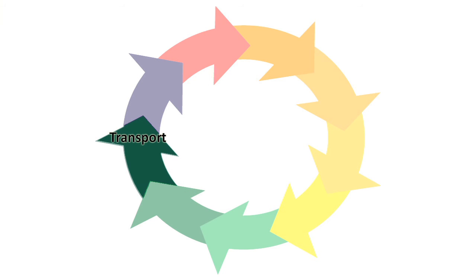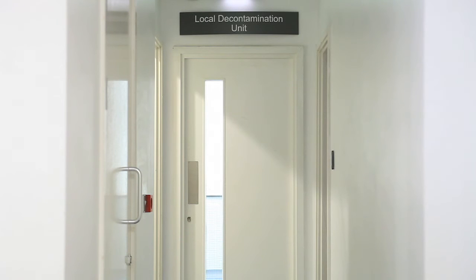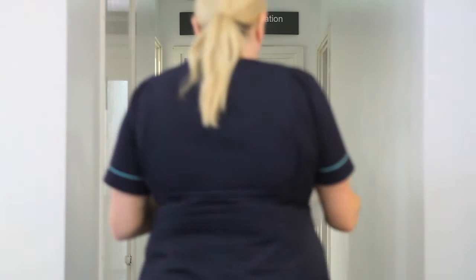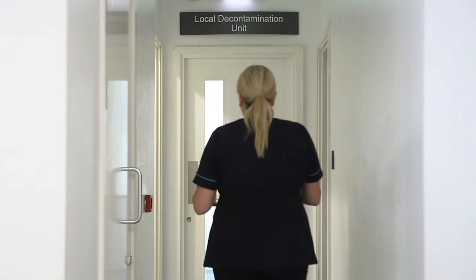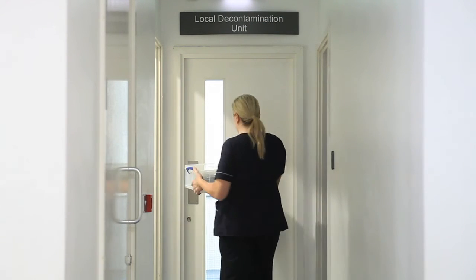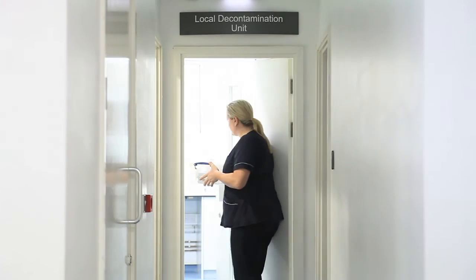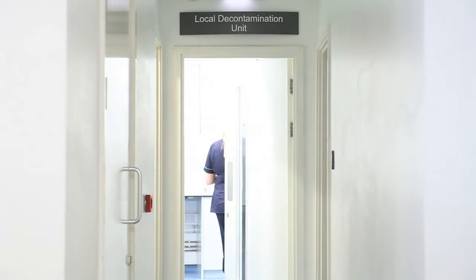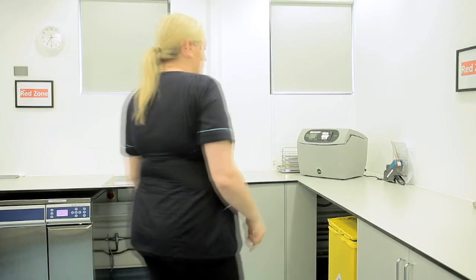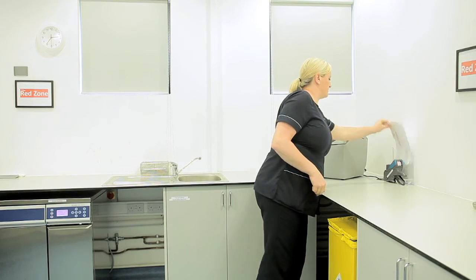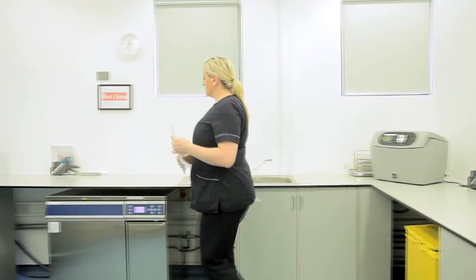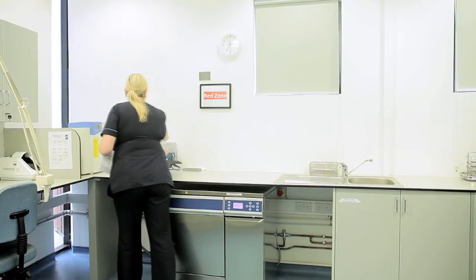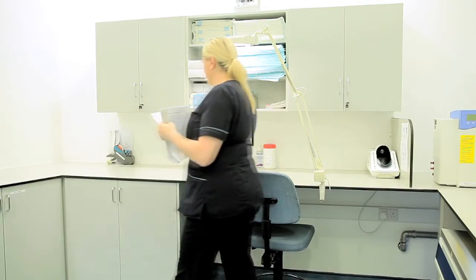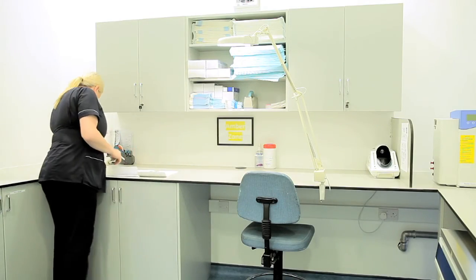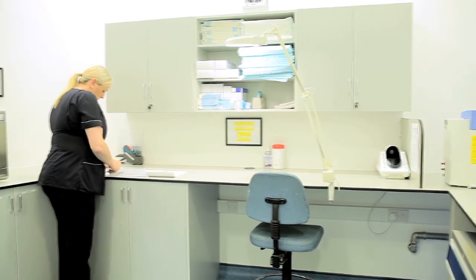The next step of the life cycle is number 10, transport. This is where used RIMD are returned to the local decontamination unit after use to commence the decontamination life cycle process. At the end of the working day, ensure that all graph printouts and related test results from all machines in the LDU are logged and stored so that they can be easily retrieved should they be required. Storage of these records is a requirement of the HSE standards and recommended practices.